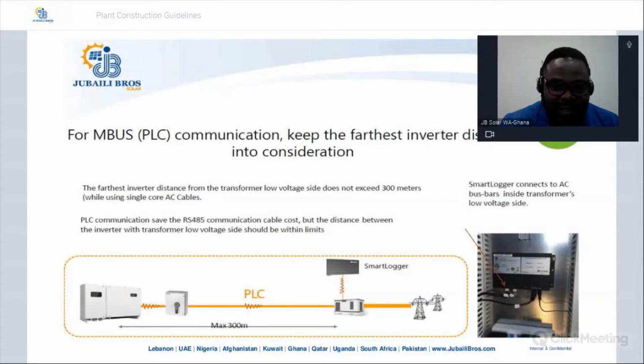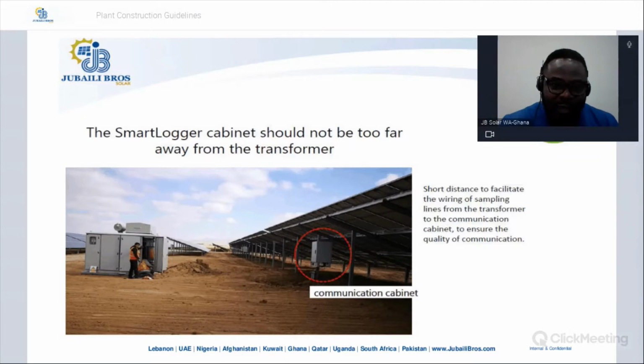If it's away from it, then you are going to further increase the distance of the communication between the transformer and the smart logger. Remember, we already have a limitation from here. So if you extend this distance more, you are going to lose some communication power. It's very important. That's why we are stating something like this. This is a fair distance, okay? Fair. But further away from this, we don't advise. Make sure that the smart array controller that has the smart logger is always closer to the transformer. Very, very important. Let this communication cabinet be closer.